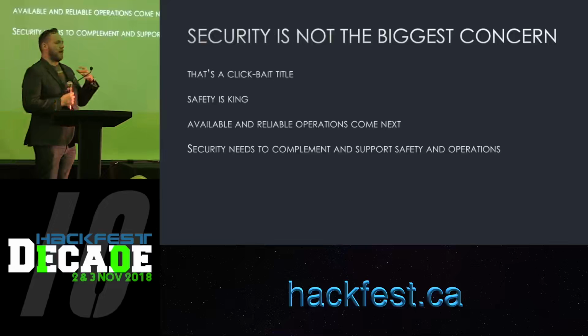Default, hard-coded and common credentials are everywhere. You can go to ABB or any PLC manufacturer, Schneider, and just get a list of their default passwords, or find Axis cameras whose admin username is always root with no enforcement on the password - no lockout, so you just hammer it until you find it. And everything's in plain text for the most part.